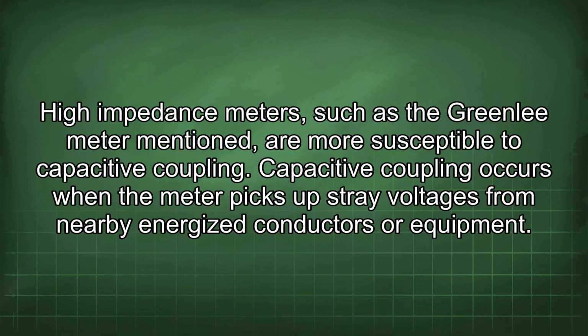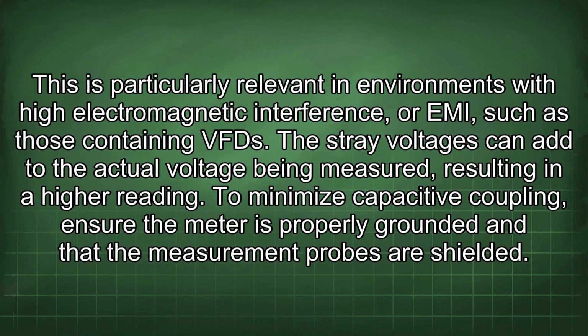High-impedance meters, such as the Greenlee meter mentioned, are more susceptible to capacitive coupling. Capacitive coupling occurs when the meter picks up stray voltages from nearby energized conductors or equipment. This is particularly relevant in environments with high electromagnetic interference, or EMI, such as those containing VFDs. The stray voltages can add to the actual voltage being measured, resulting in a higher reading. To minimize capacitive coupling, ensure the meter is properly grounded and that the measurement probes are shielded.